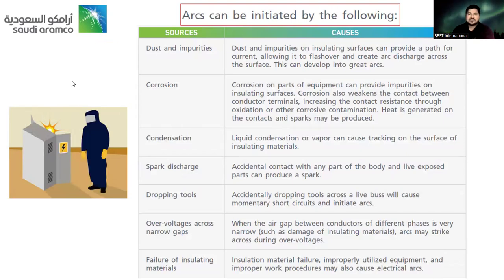Now, how can arcs be initiated? Just bear in mind, there could be plenty of sources, maybe dust and impurities, because that's why we always need to make sure our panels and all sorts of electrical systems are dust free, and we should seal and design in a way that dust cannot enter the systems. Even corrosion is another: any part, including the conductors, panel boards, breakers, or any metal which we are using inside or outside, must be free from any sort of rust or corrosion. Condensation is another, like liquid and different kinds of vapors that may cause tracking on the surface of insulating materials, even spark discharge, dropping tools, overvoltage, and failure of insulating materials. So these are some of the sources.